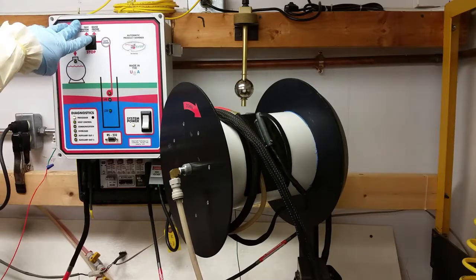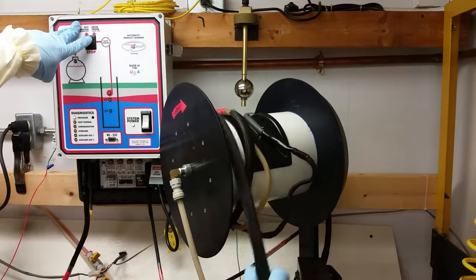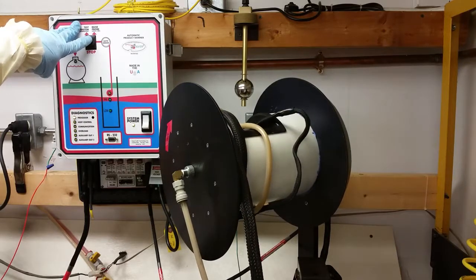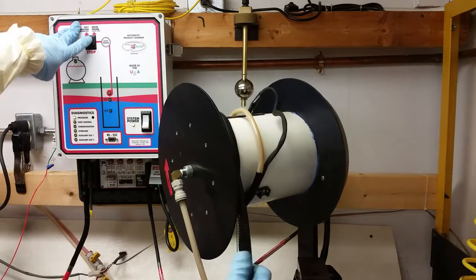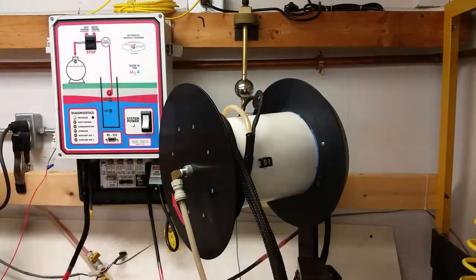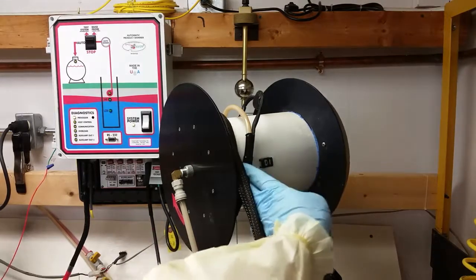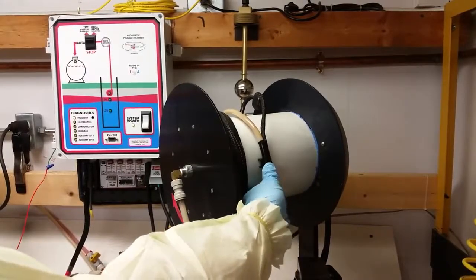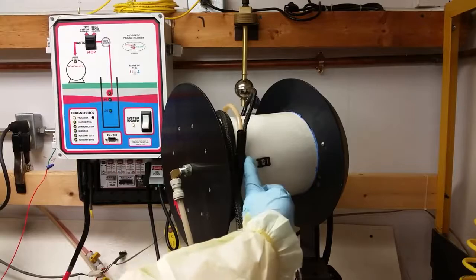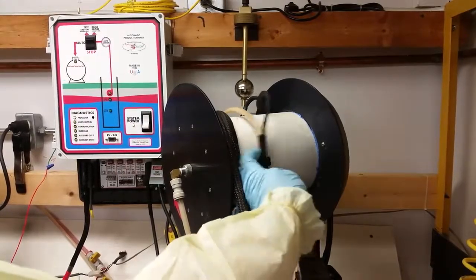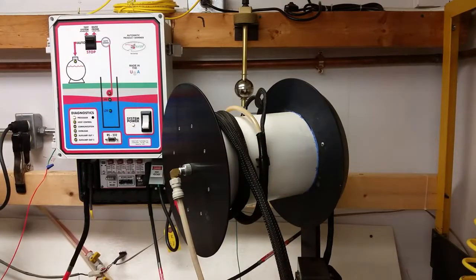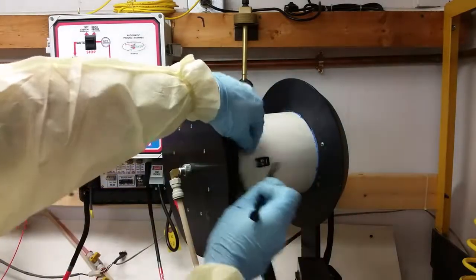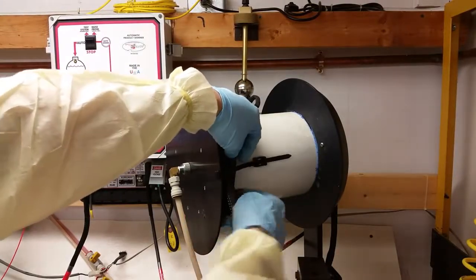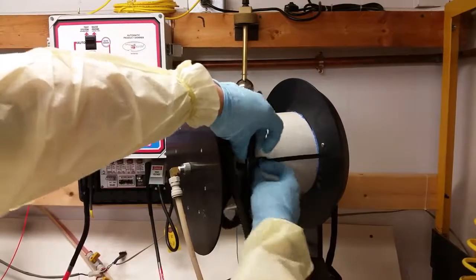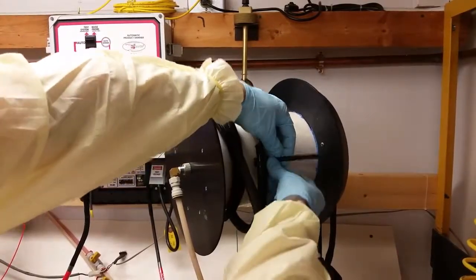You can hear that in the background. That's the pump testing. After 5 seconds, it should start reeling up the probe. Now, depending on the system you have, you may have a gray hook here that's meant to fasten the last wrap of the probe there, or one of these black parts that you can slide a zip tie through and use that to fasten this on here. I would advise using a black zip tie or that gray retainer clip. The zip tie simply slides in like that. And is secured thusly.